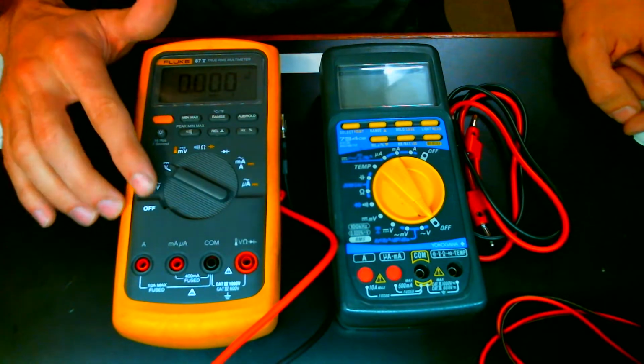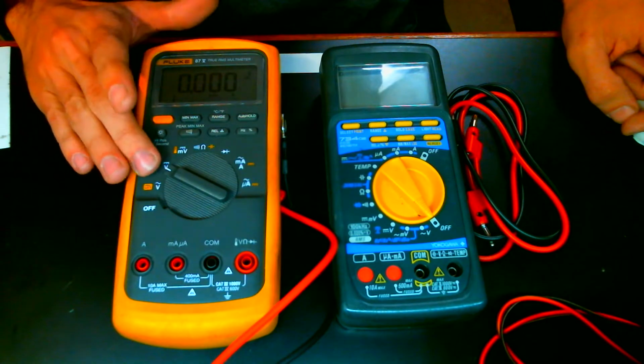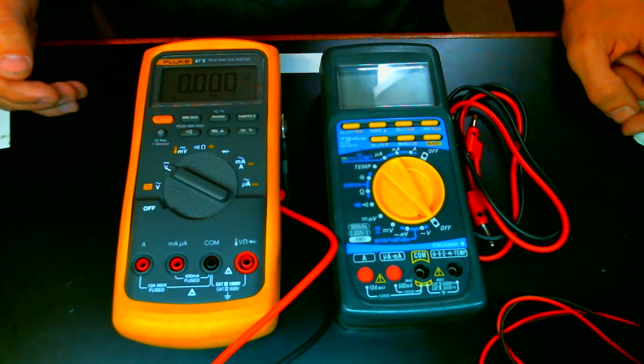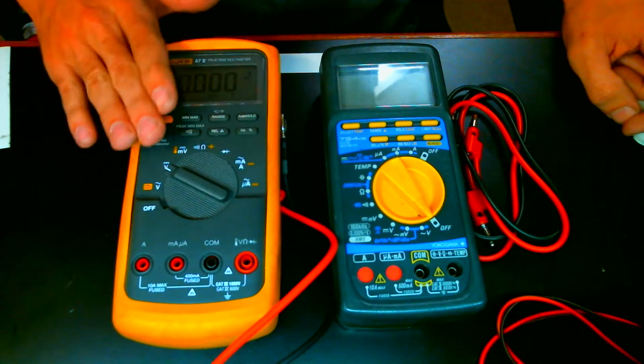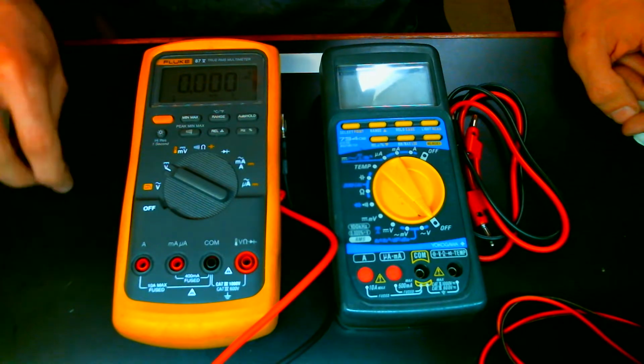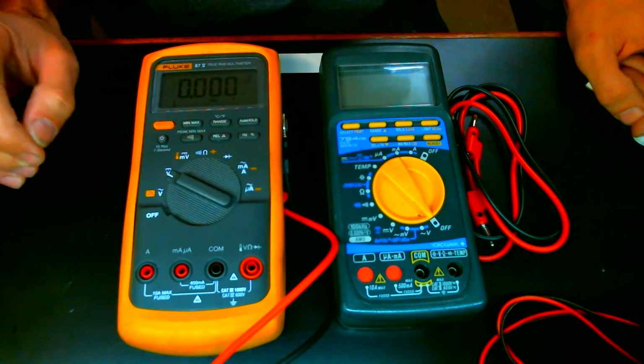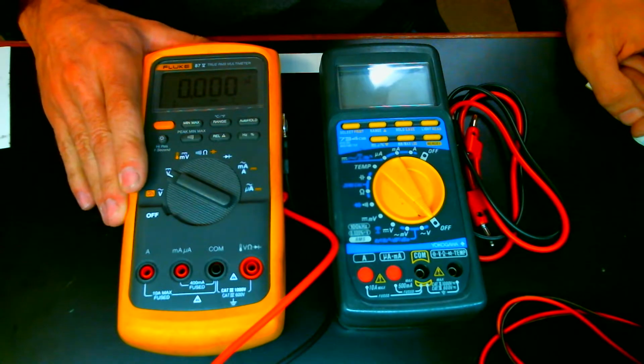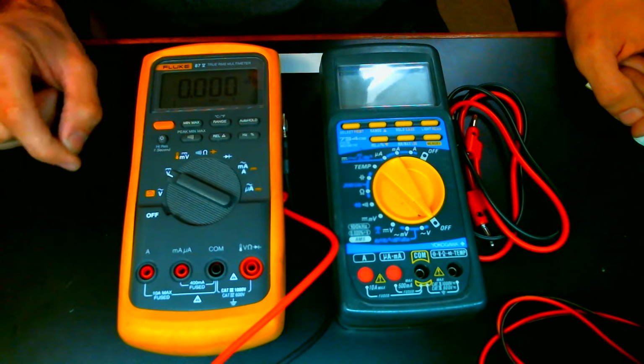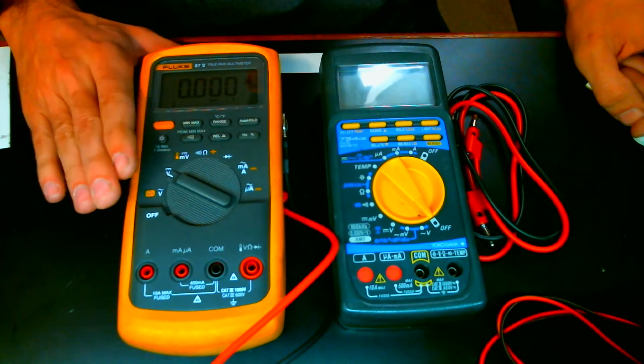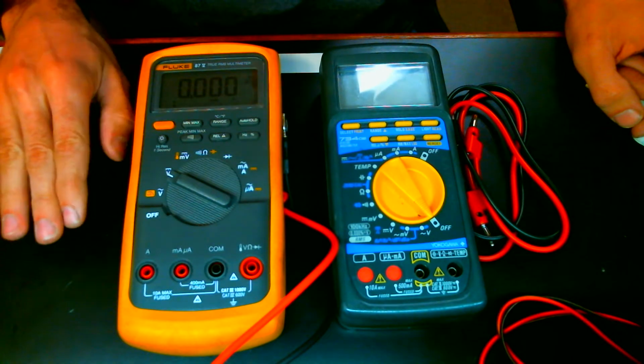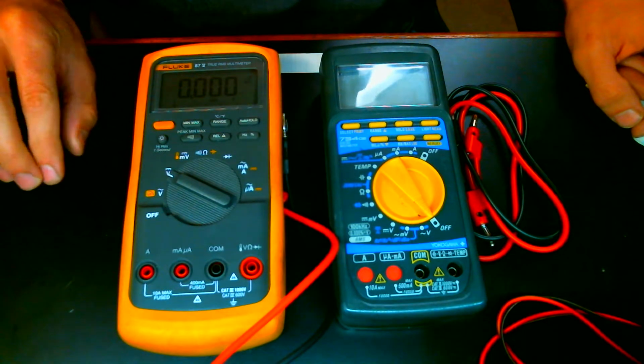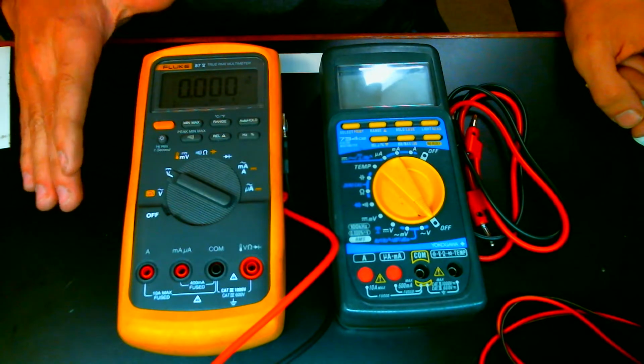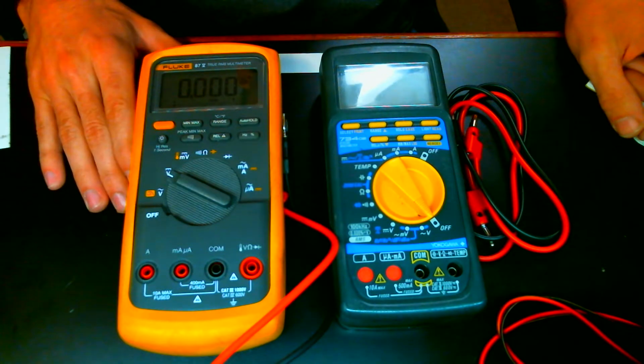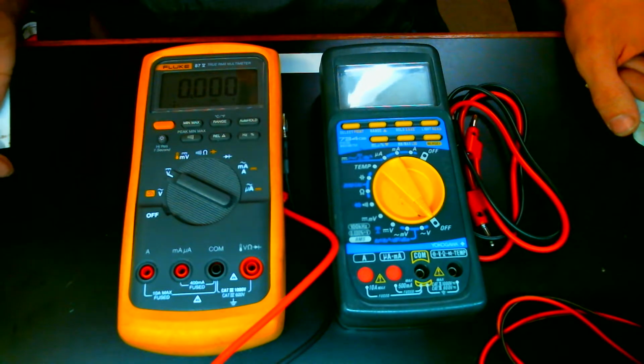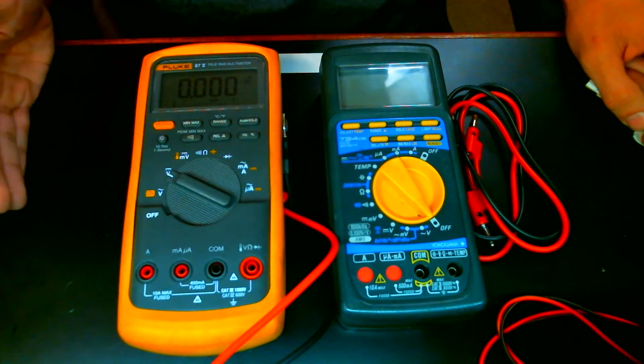Basically, all they're doing is checking it to the standards, and if the meter checks out to be within spec that the service manual will state it needs to be at, they don't have to touch anything on this meter. They'll give you maybe a table of offsets and a certificate of calibration to show that this meter was in fact calibrated. It'll have a date calibrated, and it'll also have a due date, which is normally annually. It really depends on your use what determines if you're going to do it annually or more often or less often. Some meters you may only have calibrated once every 5 years. It just all depends on what you're using it for and whether or not you need it to be calibrated yearly or not.